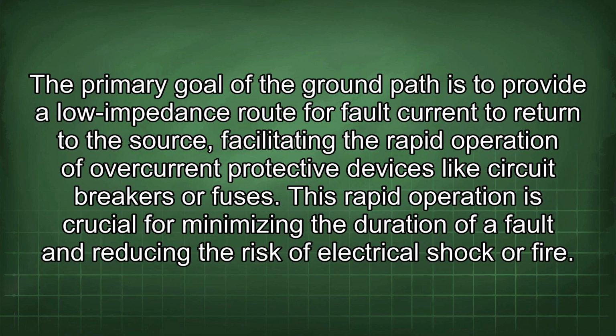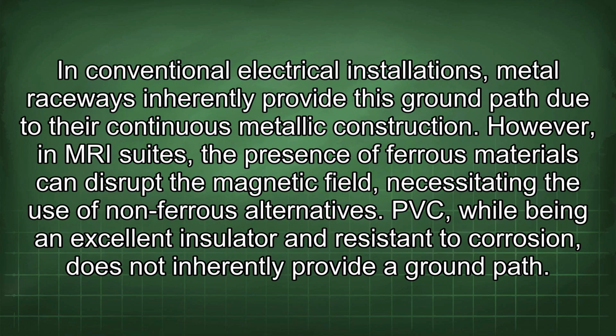The primary goal of the ground path is to provide a low impedance route for fault current to return to the source, facilitating the rapid operation of overcurrent protective devices like circuit breakers or fuses. This rapid operation is crucial for minimizing the duration of a fault and reducing the risk of electrical shock or fire. In conventional electrical installations, metal raceways inherently provide this ground path due to their continuous metallic construction. However, in MRI suites, the presence of ferrous materials can disrupt the magnetic field, necessitating the use of non-ferrous alternatives.